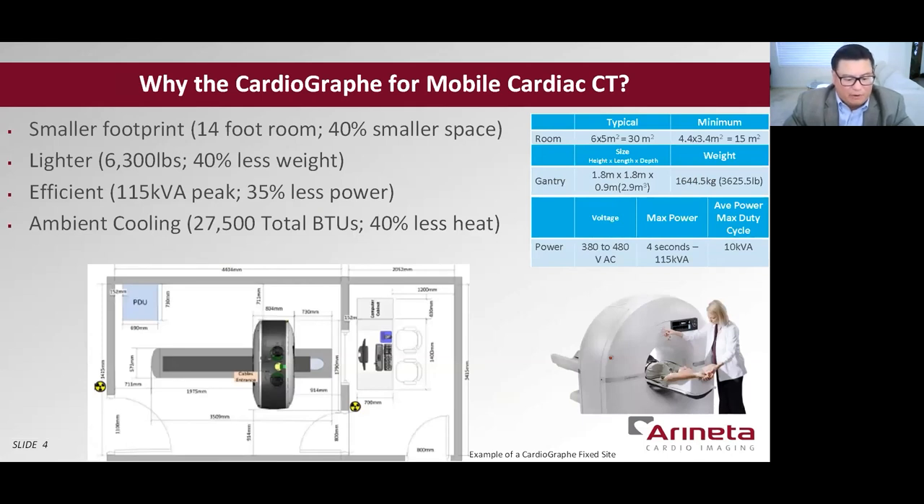So we asked ourselves, why the CardioGraphe for mobile cardiac CT? Very simply, of all single-beat, whole-heart CT scanners, the CardioGraphe has the highest temporal resolution, a 14-centimeter detector for coverage, and the best service and support in the rural communities. It has a 40-percent smaller footprint for limited mobile spaces. It's 40-percent lighter — or 2,400 pounds lighter than most CTs — making it easier to transport. It consumes 35-percent less power and generates 40-percent less heat to burden the air conditioners. The combination of all these elements makes the CardioGraphe the top mobile selection for rural.